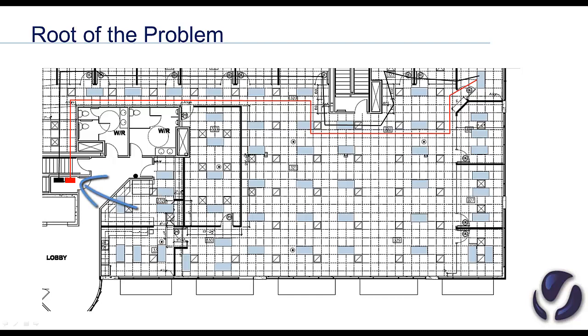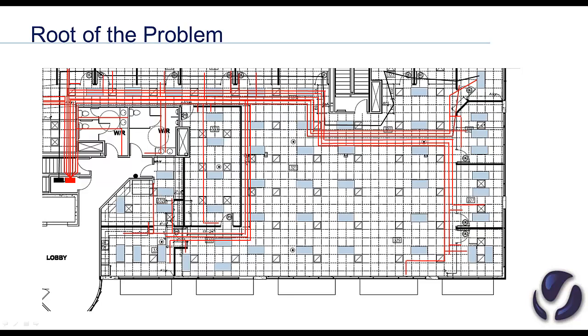Again, this is an occupied building with ceiling tiles, furniture, people, and all the considerations of a retrofit. We also have to pull a low voltage 2-conductor cable along with the new switch leg, remove the old light switch, fish this cable down the wall, and install a low voltage push button so that the occupant in this room can turn the light on and off. Industry standard labor burden for this one lighting control circuit is 3 to 6 hours. And of course, we're not talking about one lighting zone, we're talking about many zones. The labor costs keep rising.